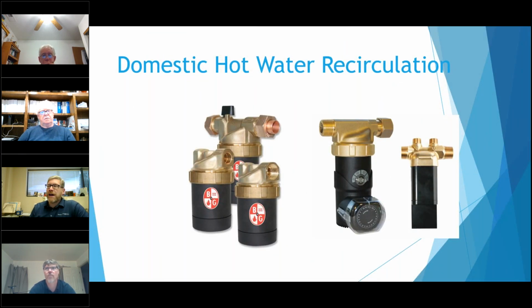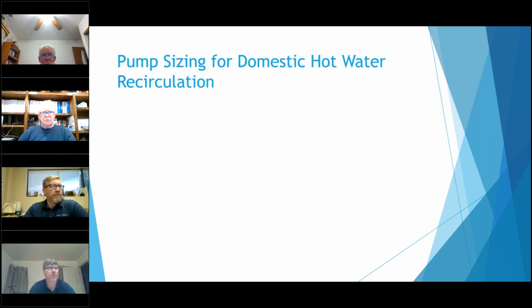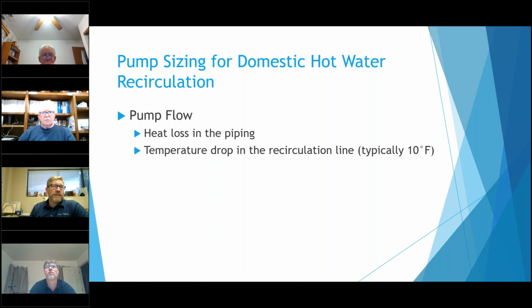Another system is domestic hot water recirc pumps. A little bit different on this. So the way the pump flow is set, it's basically a heat drop in the piping. A lot of them are insulated, but there is going to be some heat loss in it. Typically, the way they design these are about a 10-degree delta T. So if you're sending out 140, usually comes back at 130. There's charts to depend on how well insulated the pipe is and how much. You can go certainly less. Obviously, you'll need more GPM, but whatever that chart kind of dictates, it dictates how much flow is going to go through.